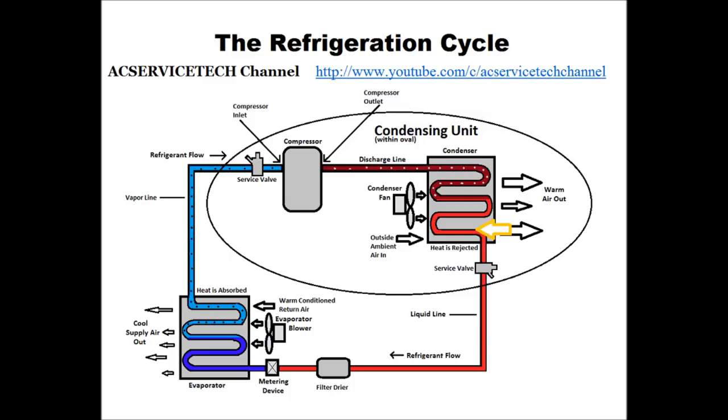The condenser is where subcooling takes place. Subcooling is the temperature decrease in liquid form in the condenser, to where it comes out past the service valve. There's only one spot where there's liquid in the condenser coil, and it's after the saturated state, where it comes out. We always take a temperature reading right next to the service valve because that's where we can get an accurate pressure reading.